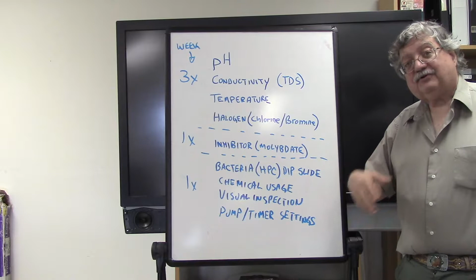You're also going to do a weekly walk-around inspection of your cooling tower, using a checklist prepared by whoever wrote your Maintenance and Prevention Plan book. It's basic: it asks if there's overspray, leaks from the cooling tower, any observable slime or algae, and so on. That basic inspection has to be done once a week.